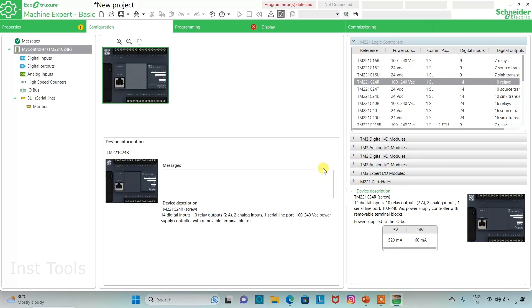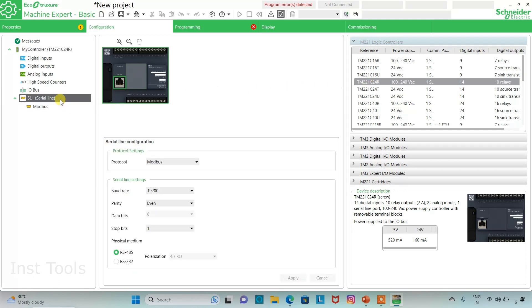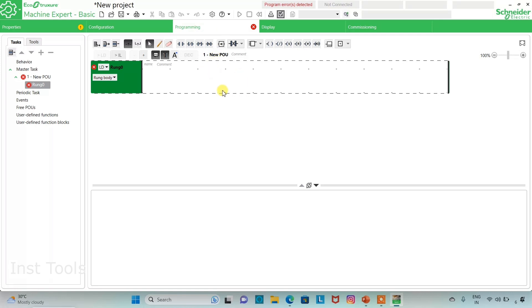I will drag it here. Click Yes to replace, so we have configured the device as TM221C24R. Then I will go to the Serial Line SL1 and set the protocol as Modbus and click Apply. After that I will go to the Programming tab, which is the area where we can draw the ladder diagram.